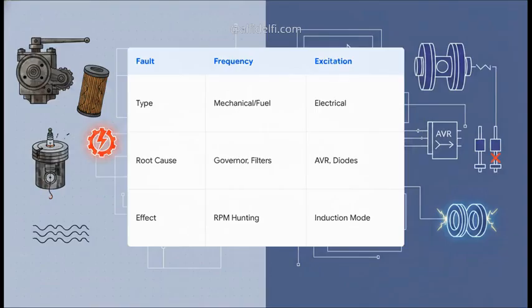Let's methodically break down the root causes. Frequency hunting is basically born from mechanical and fuel issues. You're looking at things like a governor actuator failure, maybe clogged fuel filters, misfiring cylinders, or even heavy rolling causing fuel slosh in the tanks. Put simply, it's a mechanical failure that's manifesting electrically.